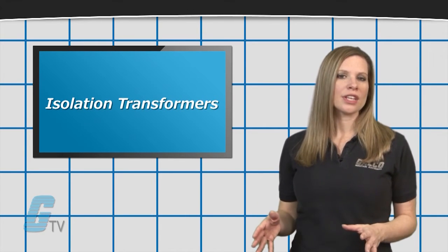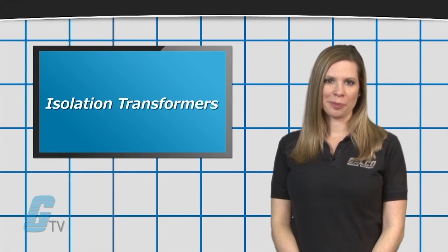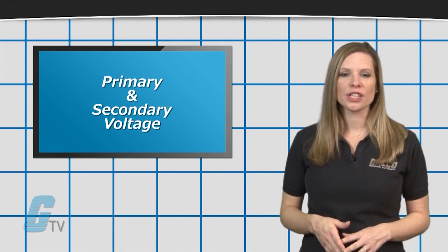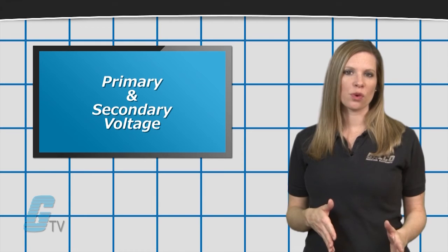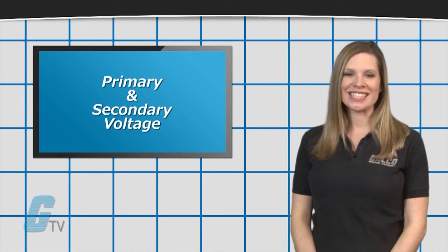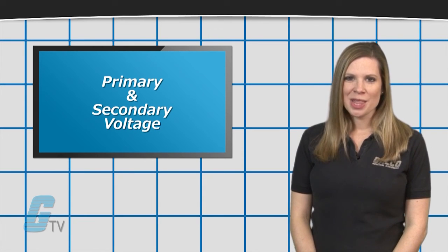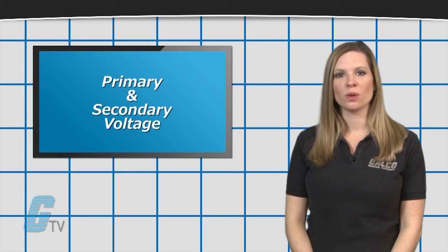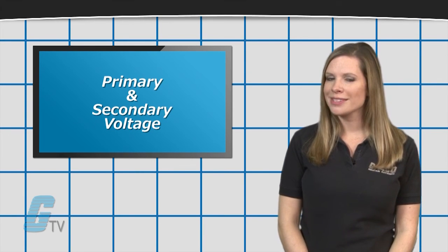So there will be no need to oversize the transformer. You will also want to look at the primary and secondary voltage to verify that the transformer is compatible with the existing power system. The primary voltage should match the line in voltage and the secondary voltage should match the requirements of the drive.